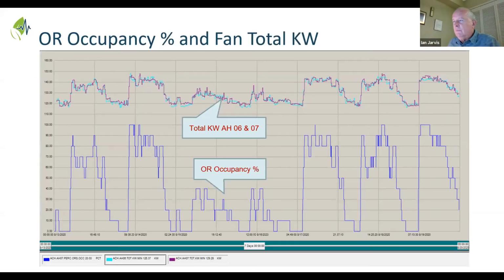Franz and Amandeep just started looking at some of this, but the purpose of this is more, you can see the actual OR occupancy on the chart on the bottom, and what's happening to the fan kilowatts there. And as the fan kilowatts go up and down, so the cooling energy, the reheat energy, the preheat energy, humidification, all those numbers fall around in accordance.